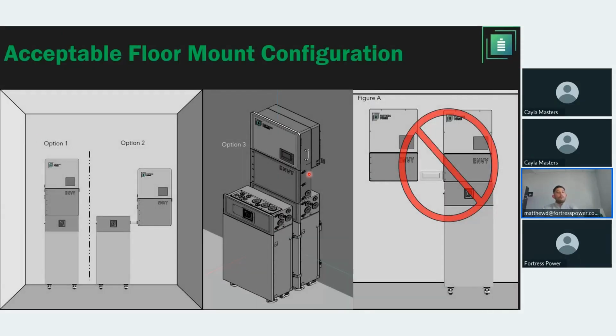These are the acceptable floor mounted configurations. You can stack the ENVY on top of a battery, or you can stack the ENVY on the side of the battery, which would be a perfect solution if, again, a lot of the systems don't necessarily require that disconnect or that top compartment where the ENVY sits. You can just stack the inverter on the side. And then option 3 is installing the battery right in front of the other battery.